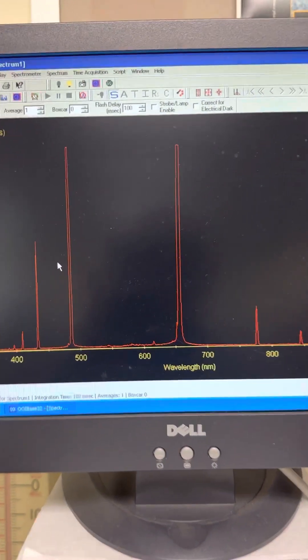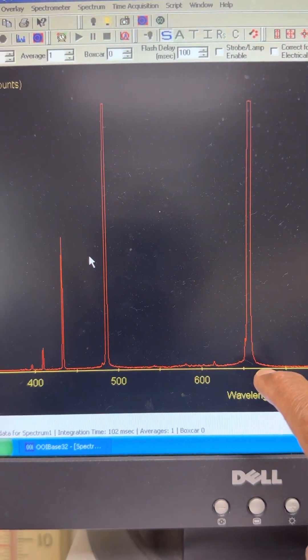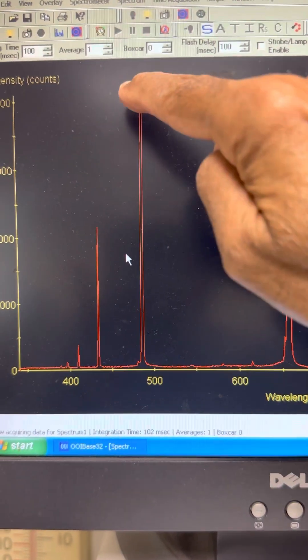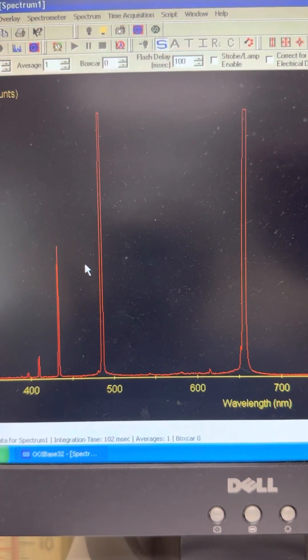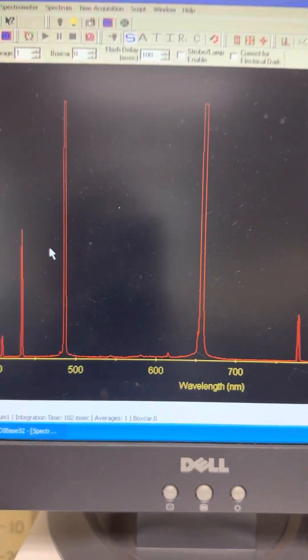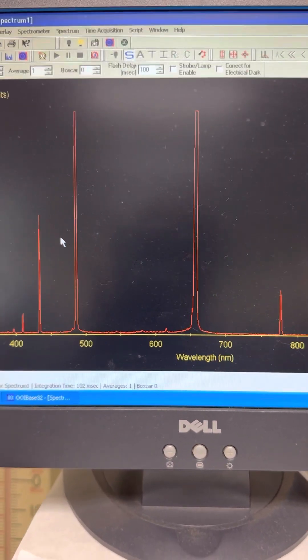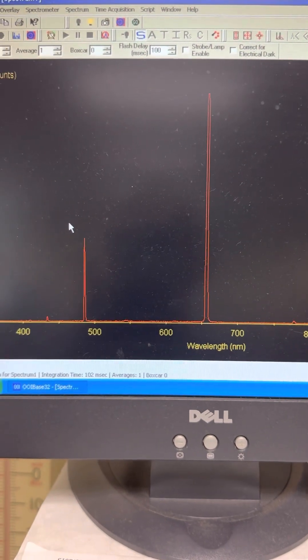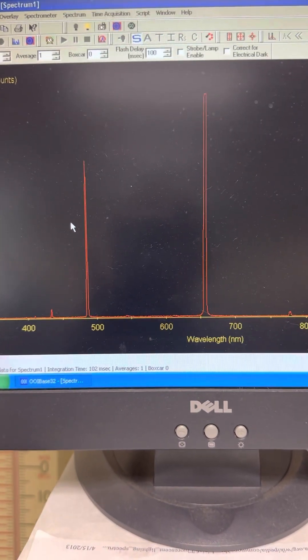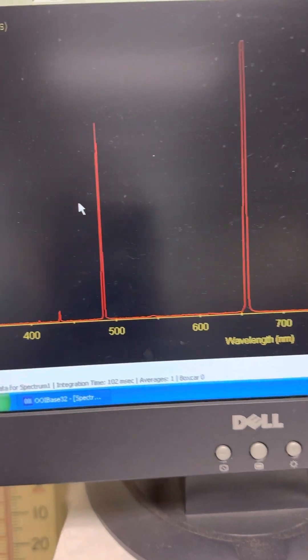The head is close to the light now and you can see all the peaks. We are going to concentrate on the visible spectrum, but the problem is these two peaks have the highest intensity count. To measure the intensities proportionally, we need only one of them to have the highest intensity. Let me make some adjustments to the head so that only one shows as the highest peak — something like that. Now we have basically only one with the highest intensity and the others are less.